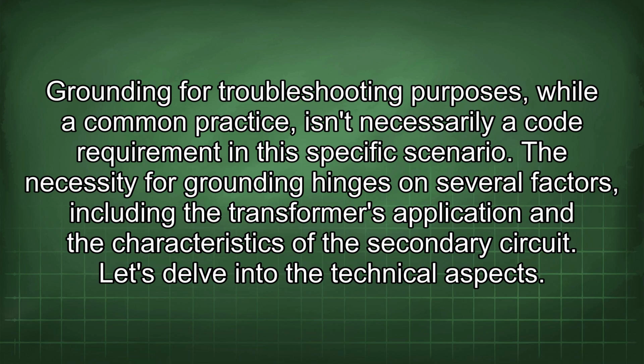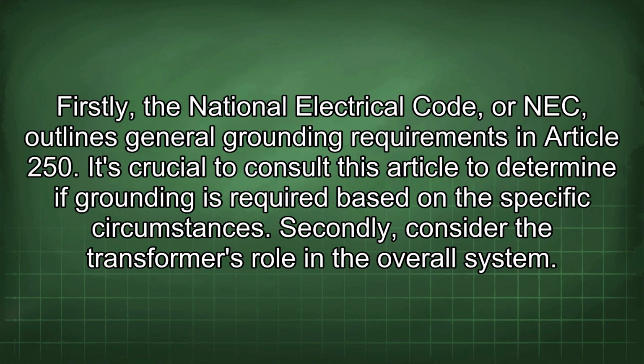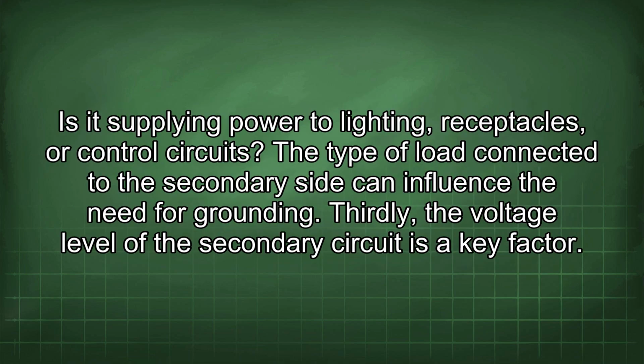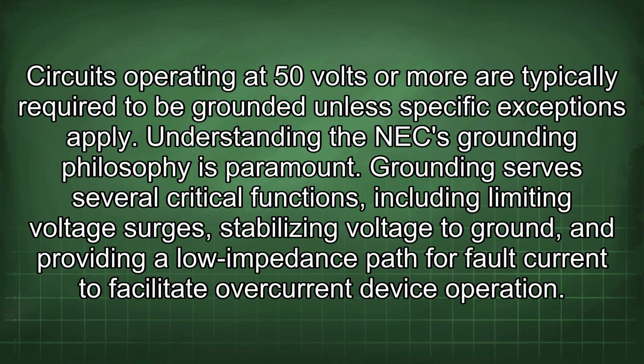Let's delve into the technical aspects. Firstly, the National Electrical Code, or NEC, outlines general grounding requirements in Article 250. It's crucial to consult this article to determine if grounding is required based on the specific circumstances. Secondly, consider the transformer's role in the overall system. Is it supplying power to lighting, receptacles, or control circuits? The type of load connected to the secondary side can influence the need for grounding. Thirdly, the voltage level of the secondary circuit is a key factor. Circuits operating at 50 volts or more are typically required to be grounded unless specific exceptions apply.